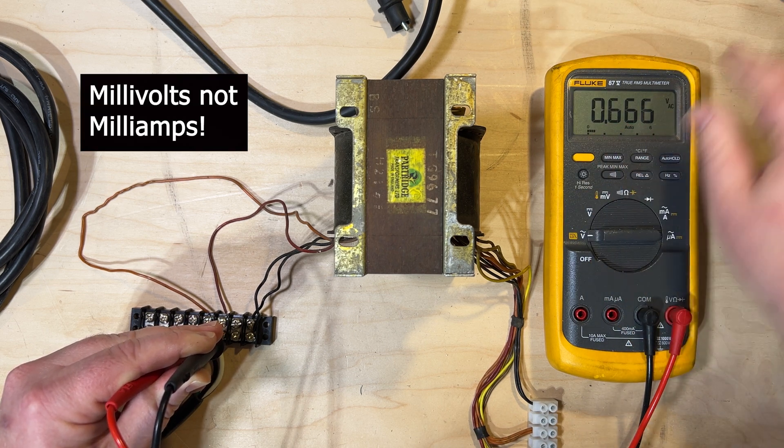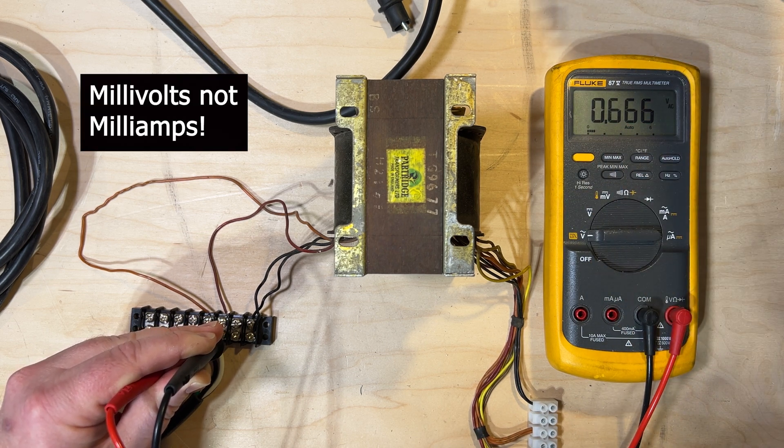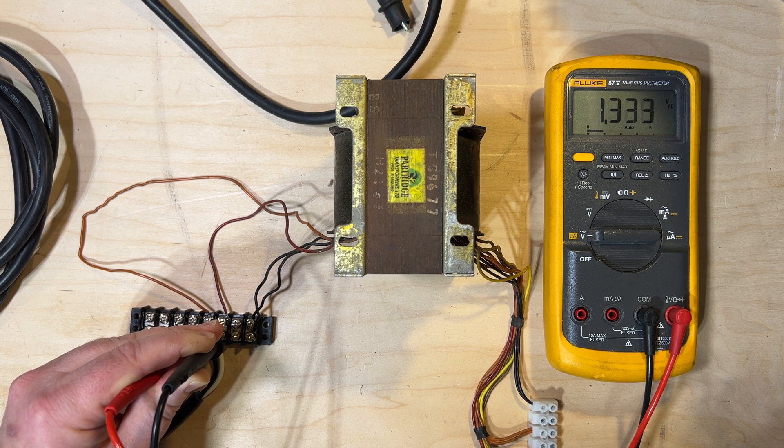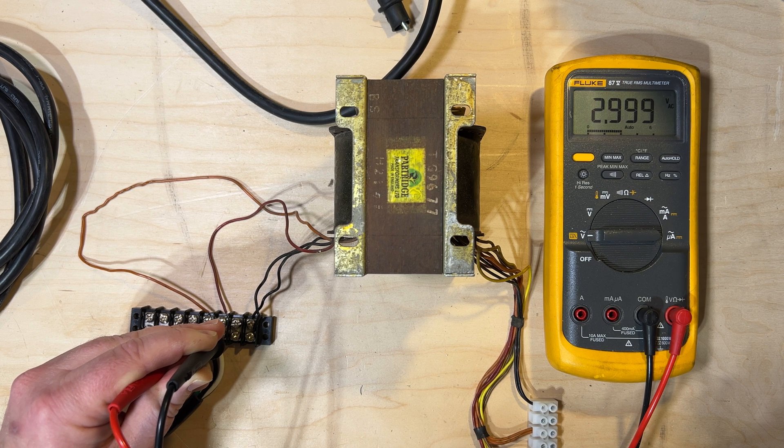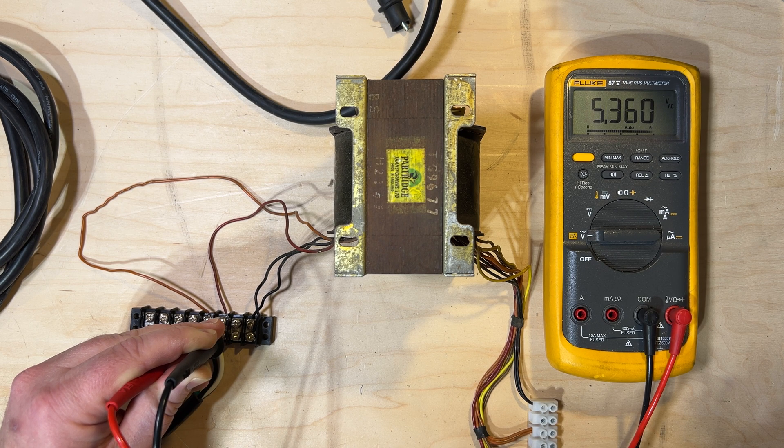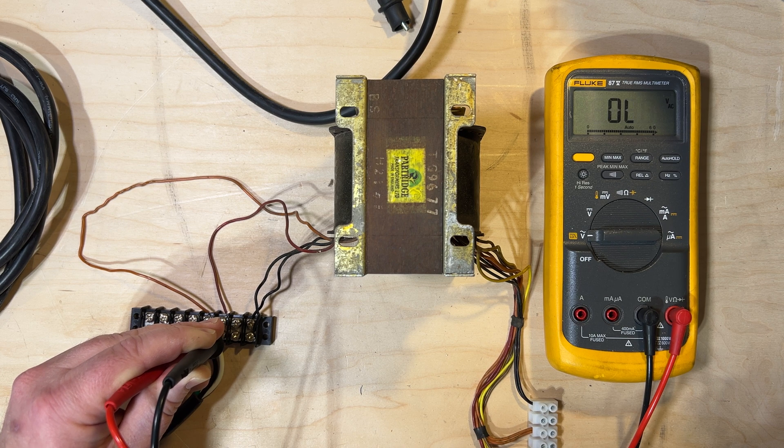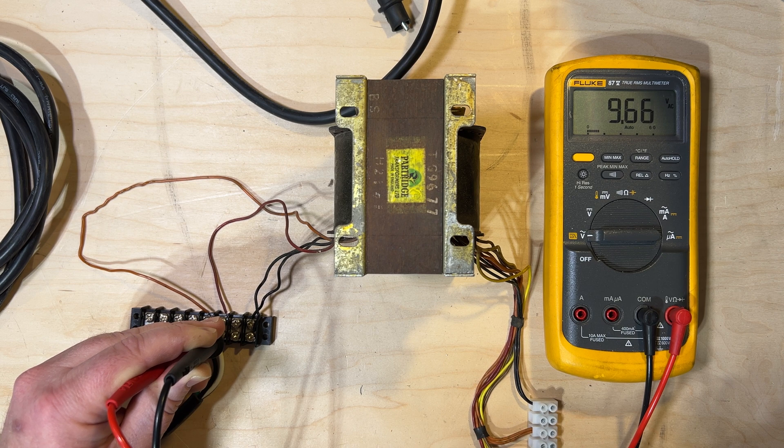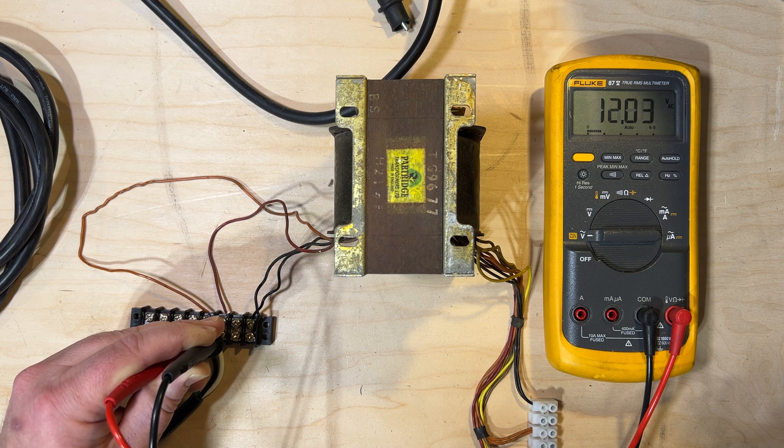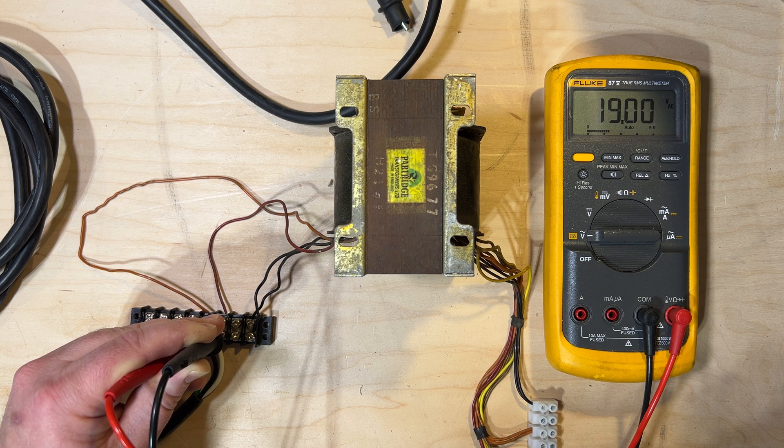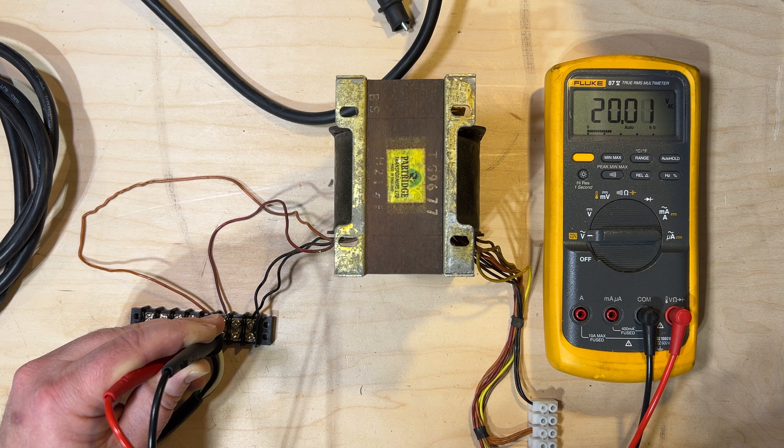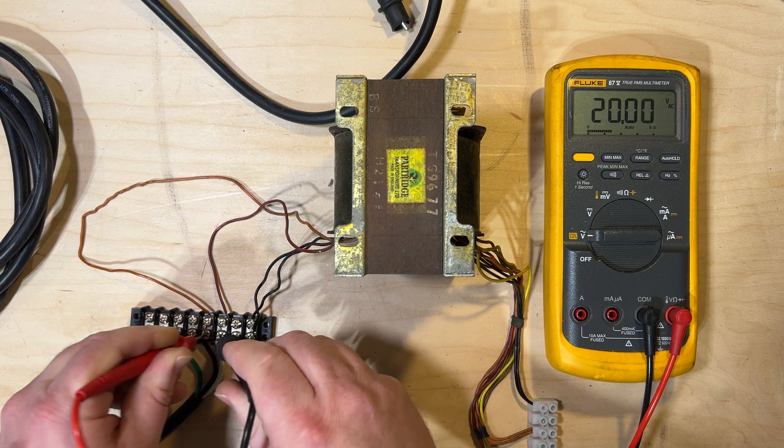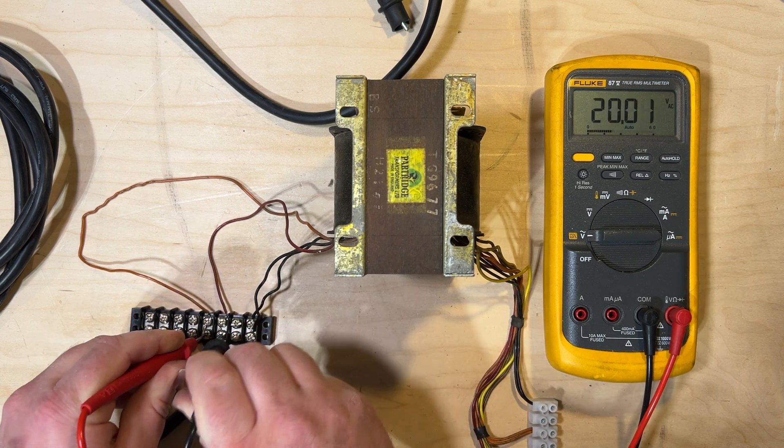I'm going to bring it up to about 20 volts. And there's a really great walkthrough of a similar type of test on RG Keene's website, geofex.com. If you're interested in seeing a detailed procedure for different types of transformer test, he lays it out pretty well. So, let's get this up to about 20 volts. Okay, perfect. So, we're sending 20 volts in to our primary side of the transformer.